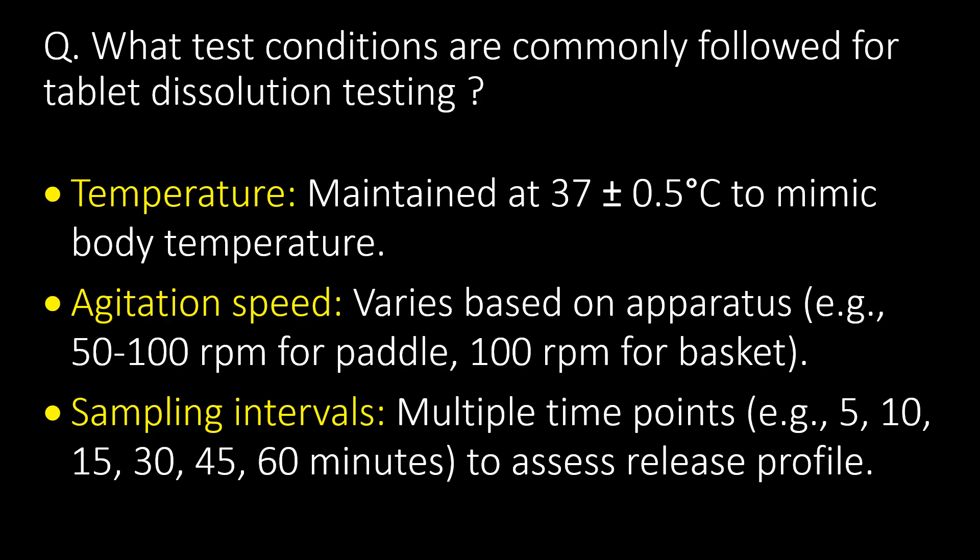What test conditions are commonly followed for tablet dissolution testing? First, temperature is maintained at 37 ± 0.5°C to mimic body temperature. Second, agitation speed varies based on apparatus — for example, 50–100 rpm for paddle type and 100 rpm for basket type. Third, sampling intervals are taken at multiple time points — for example, 5, 10, 15, 30, 45, and 60 minutes — to assess the release profile.